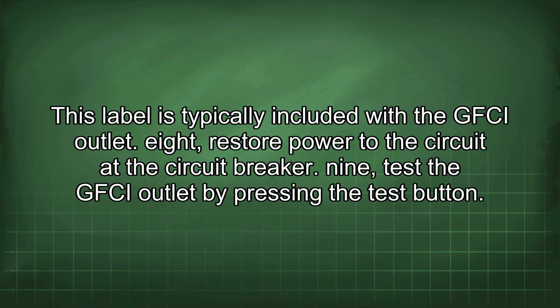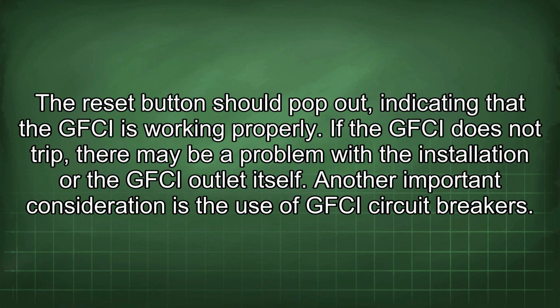8. Restore power to the circuit at the circuit breaker. 9. Test the GFCI outlet by pressing the test button. The reset button should pop out, indicating that the GFCI is working properly. If the GFCI does not trip, there may be a problem with the installation or the GFCI outlet itself.